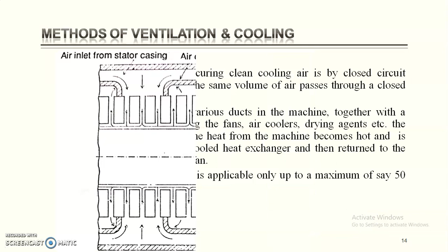Closed circuit air cooling. A complete means of securing clean cooling air is by closed circuit ventilation system. Here the same volume of air passes through a closed circuit again and again. This circuit consists of various ducts in the machine, together with a chamber below containing the fans, air coolers, drying agents, etc. The cold air, after extracting the heat from the machine, becomes hot, and it passes through a water cooled heat exchanger and then is returned to the machine by a centrifugal fan.